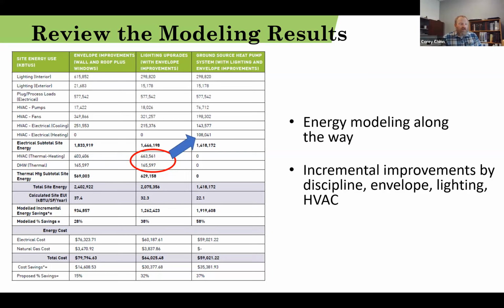We're using fiberglass windows with a U value of less than 0.2 and a solar heat gain coefficient of less than 0.2. We worked with the architect to size the height above the windows and the depth of those overhangs to really take credit for that low winter sun and to block out that high summer sun. But then we plugged it into an energy model and we were able to let the architect know your piece of this process accomplished 28% energy savings and 15% cost saving. The lighting, the electrical folks, they took us their lighting improvements upon the envelope improvements, got us to 38% energy savings and 32% cost saving.